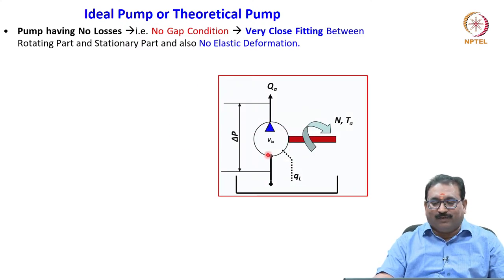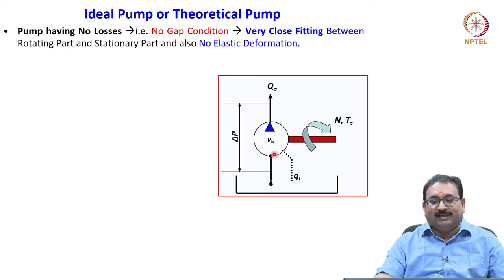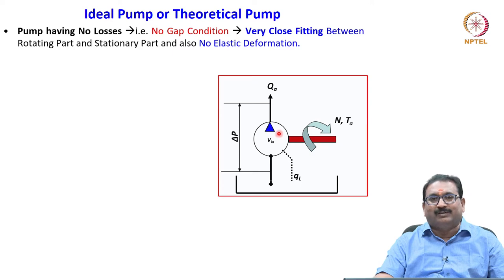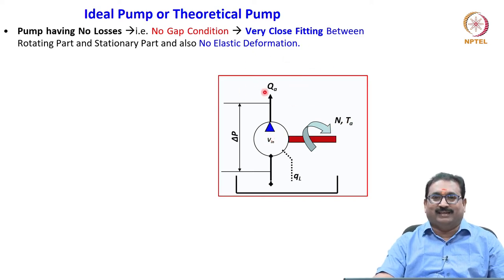I will show you here. This is a pump connected to the tank. QA is the outlet where the flow will go out due to the delta P. At the suction, there is always a vacuum and tank pressure is 1 bar. Wherever the rotating elements are, there is leakage — QL is the leakage. The pump will receive mechanical energy through N and torque to rotate, then it gives hydraulic energy.